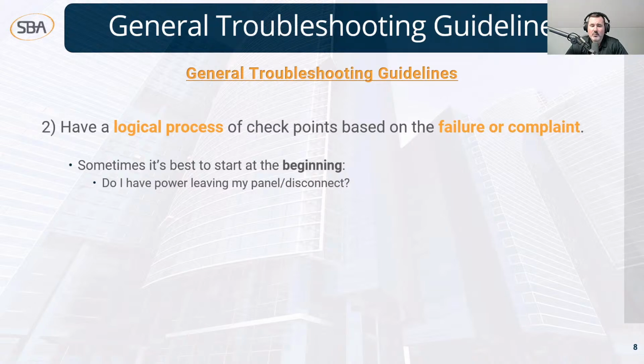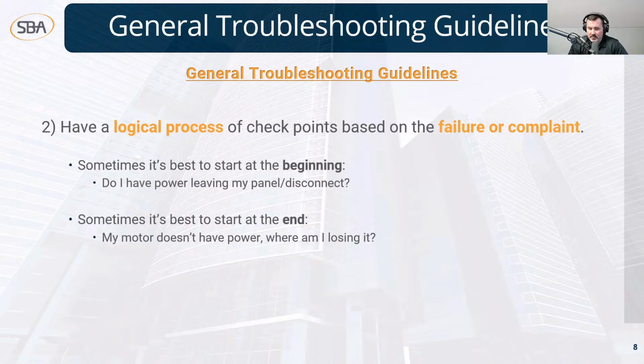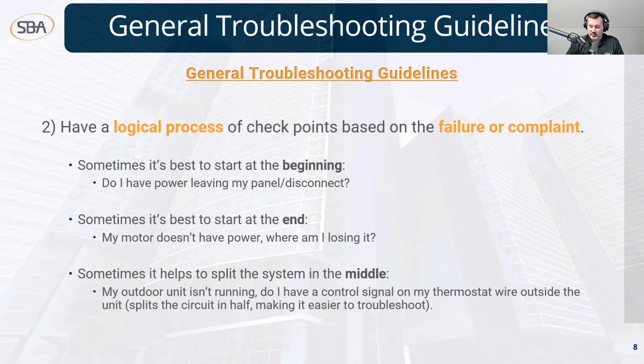Do I have power leaving my panel or disconnect? A lot of times it's actually best to start at the end, wherever the failure is. Why is my motor not running? Does it have power? If not, where am I losing it? And then there are some situations where you can split the problem up in the middle.